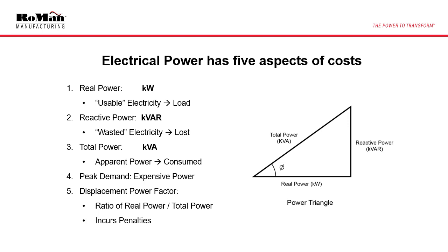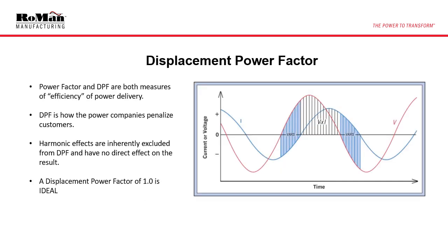During the development of IGBT MFDC, we sat down with major power companies and asked them, what exactly makes power expensive? The answer? Furnace customers get charged for kilowatts and are penalized for low displacement power factor. So what is displacement power factor? Displacement power factor, as I described earlier, is the angle between the real and reactive losses in a circuit. Essentially, it is how the current leads or lags from the applied voltage. The leading or lagging of current creates an unnecessary burden on the power company and makes electricity more expensive.